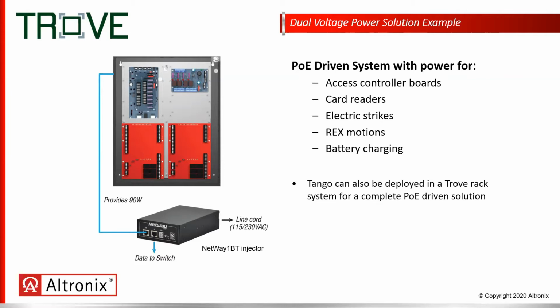So here, what we're showing is our Trove 1 enclosure, a 4-door access control system, where we are now utilizing Cat 5e or higher cable from our head end location, 100 meters, utilizing our NetWay1BT power injector, dropping the 90 watts onto the Cat 5e or higher cable.